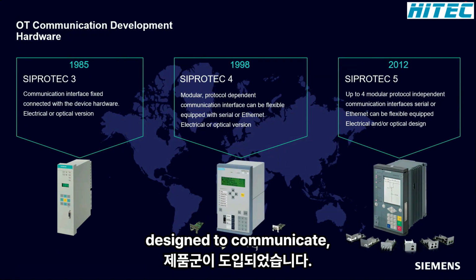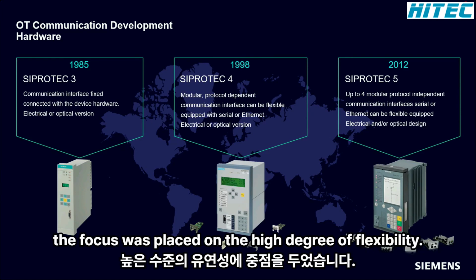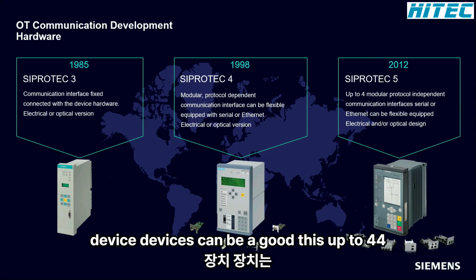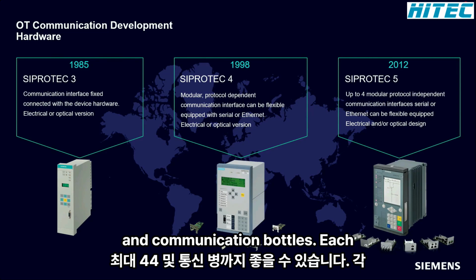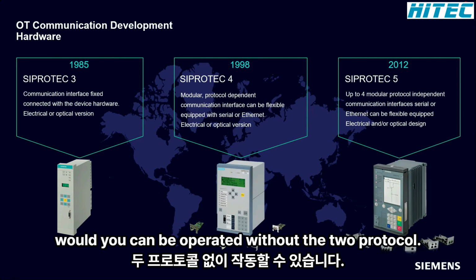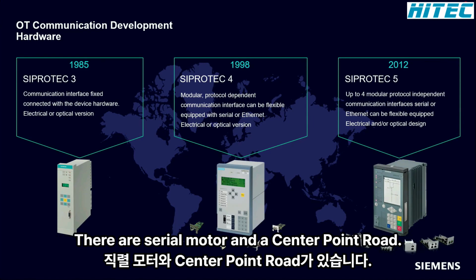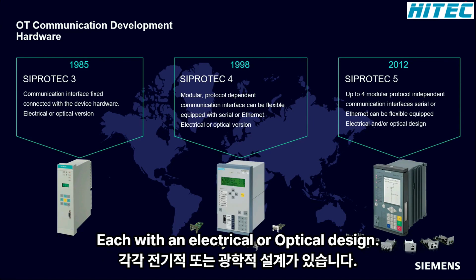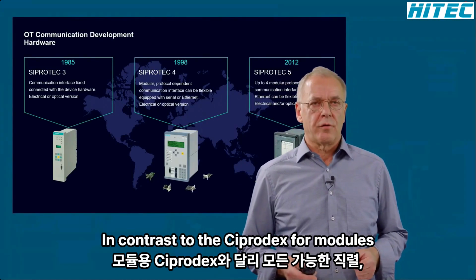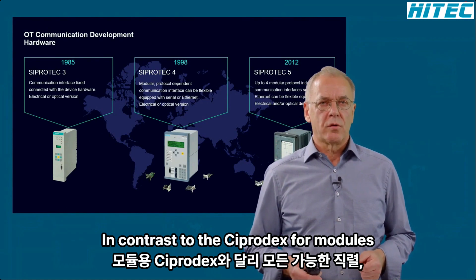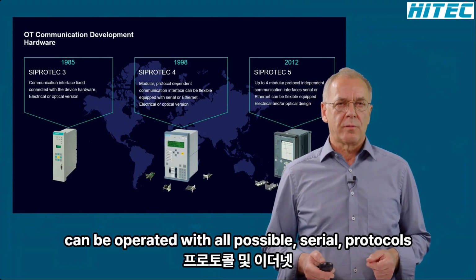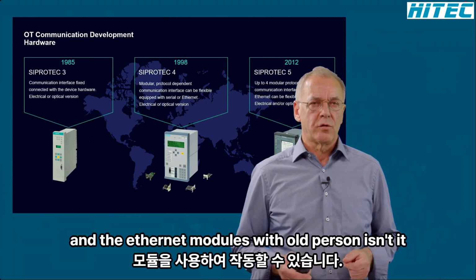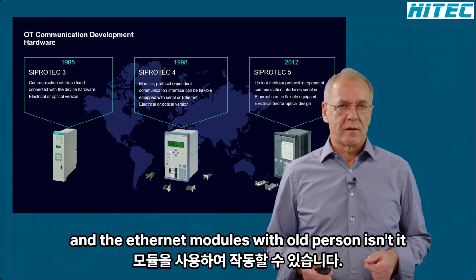Under the slogan "Designed to Communicate," the focus was placed on a high degree of flexibility. Modular SIPROTEC 5 devices can be equipped with up to 4 different communication modules. Each module can be operated with up to 2 protocols. There are serial modules and Ethernet modules, each with an electrical or optical design. In contrast to the SIPROTEC 4 modules, the serial modules can be operated with all possible serial protocols and the Ethernet modules with all possible Ethernet-based protocols.